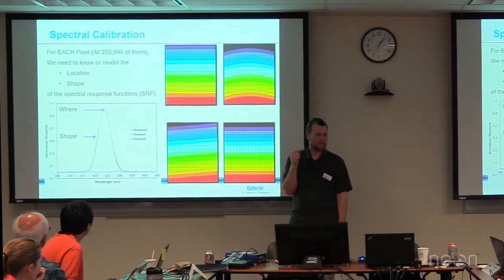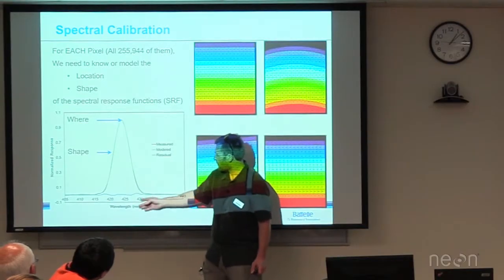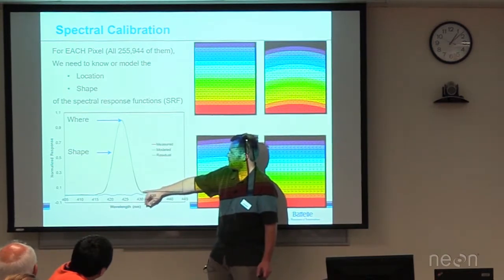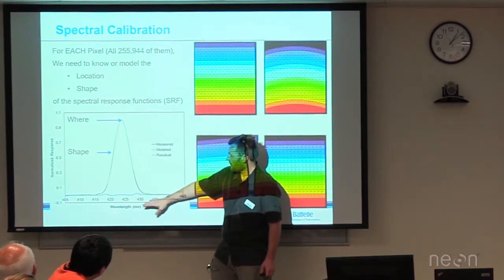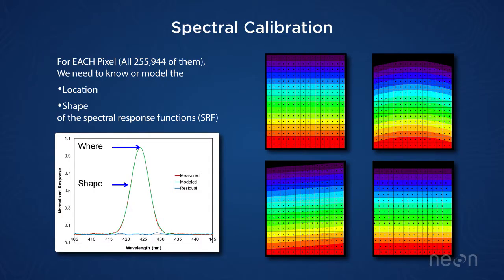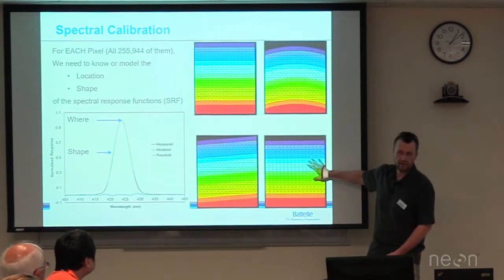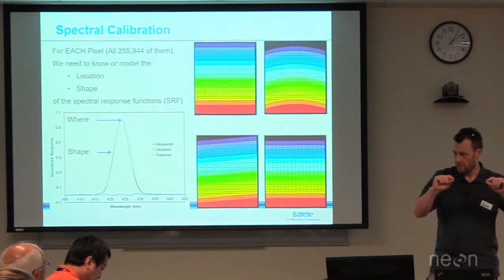Jumping into spectral calibration — there are really two things we need to know. Every pixel on that detector accepts some wavelengths of light; we have to know what wavelengths those are. Given the way an imaging spectrometer is built, those can generally be assumed to be a Gaussian spectral response function. Here we have a few different measurement techniques: the red curve is measured, the green is modeled, and the blue is the residual. In this case a Gaussian spectral response function did a good job. What we want to know is whether that's the right assumption, where the band center is, and the width. We want a situation where the same wavelength falls all the way across a given row of pixels.